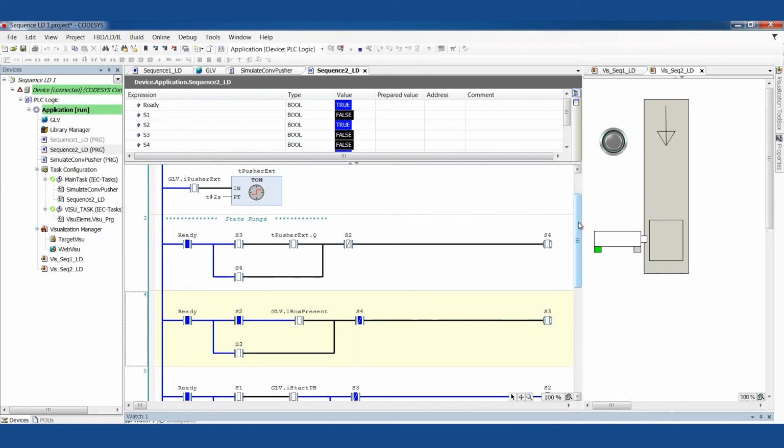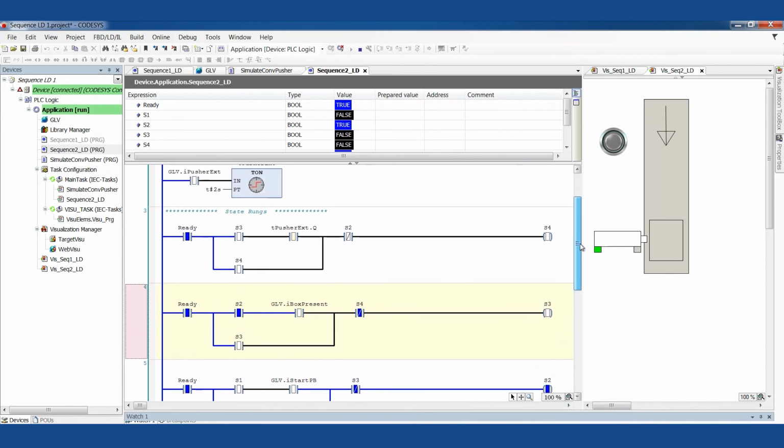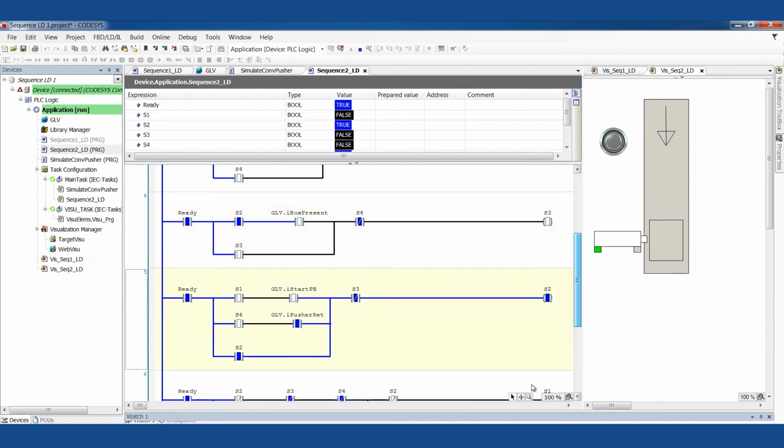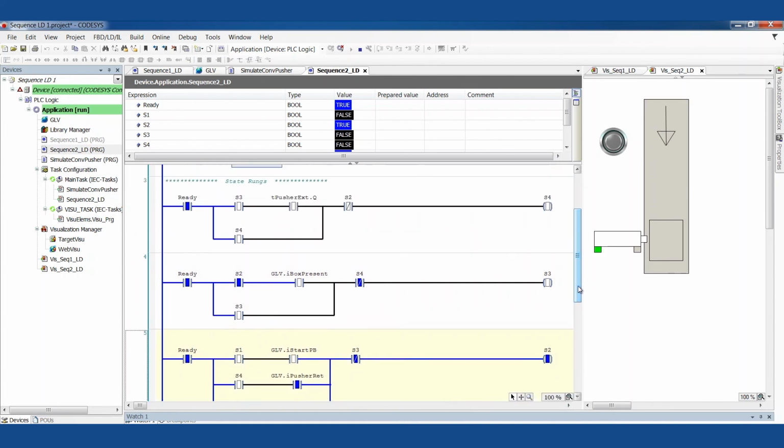Now, what's this good for? What's it not good for compared to other ways of sequencing? Now, this is where I give you my opinion. I think this is really good for teaching because it's a nice, concise process. Start to finish, we can make a sequence. We can understand how it works. We can talk about having to have these rungs out of order, and you will see some of that in the real world. And I think it's fairly easy to understand. It's got this standard rung structure that says start conditions, latch, stop conditions. To turn this thing on, we're going step by step, 1, 2, 3. There's a lot of simplicity to it, and that's nice.